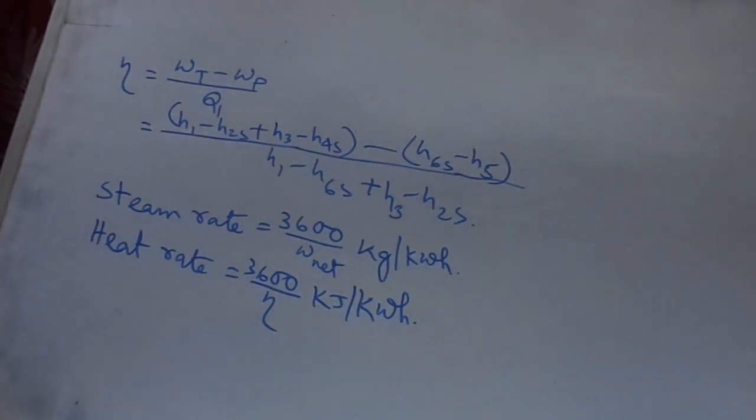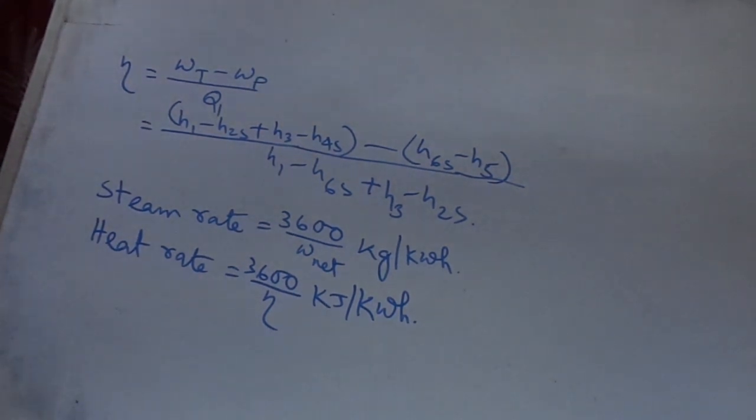Another very interesting point: by increasing the number of reheats, still higher steam pressure could be used, but the mechanical stresses increase in much higher proportion than the pressure because of the prevailing high temperature.